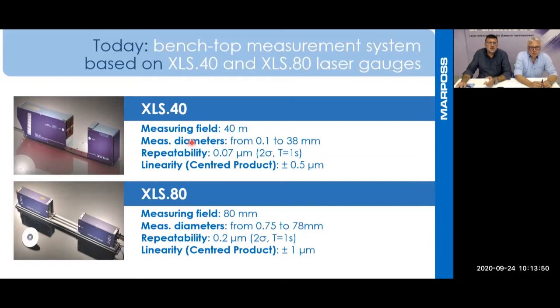The measurable diameters, normally the maximum measurable diameter is some millimeters less than the measurement field. So for the XLS40, the measurable diameters in the full range are from 0.1 to 38 millimeters. And for the XLS80 from 0.75 to 78 millimeters. These are absolute measurement systems, so they are mastered, calibrated for the full range of the measurement field without any need of recalibration when you change the diameter that you have to measure.